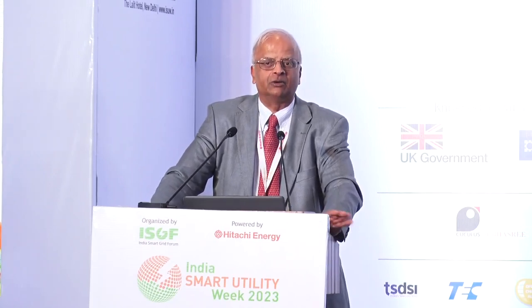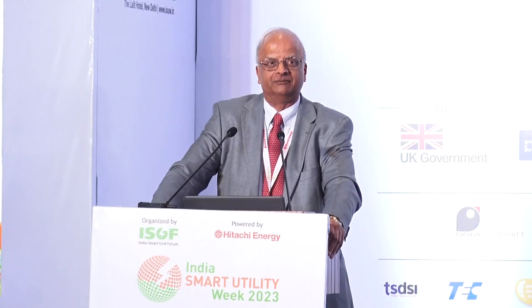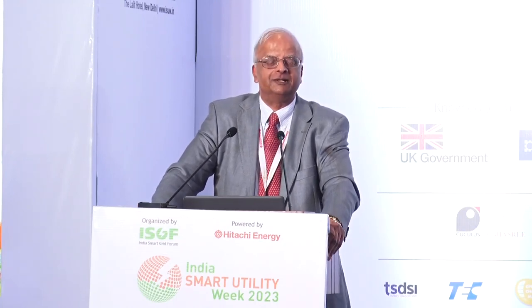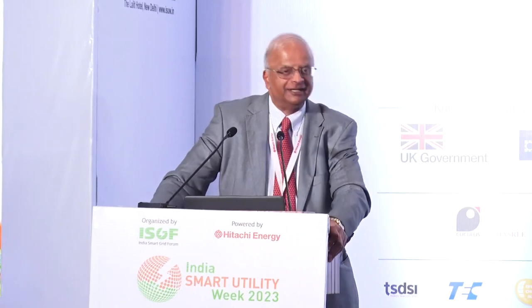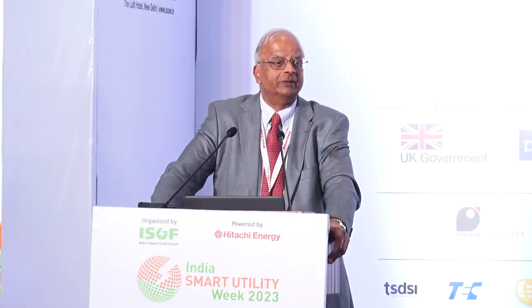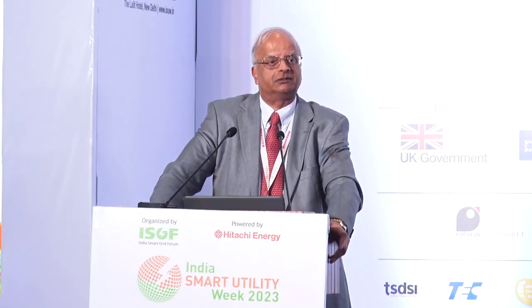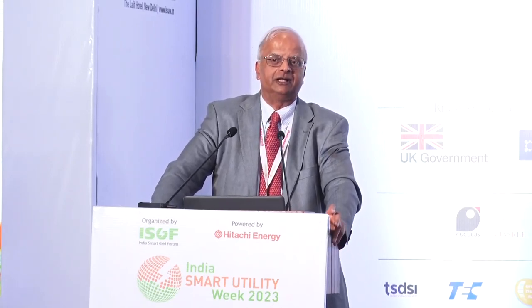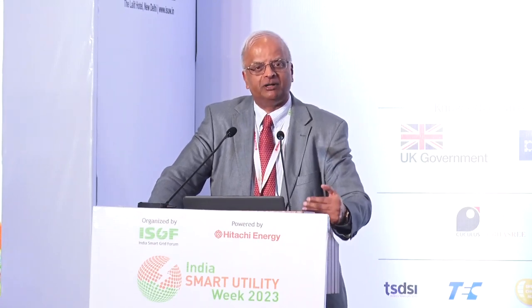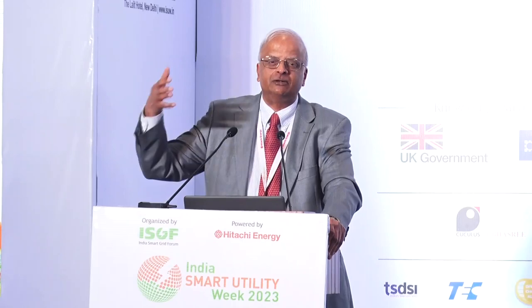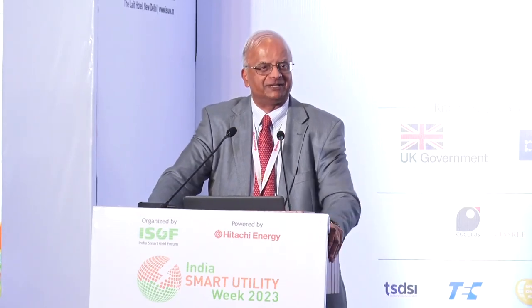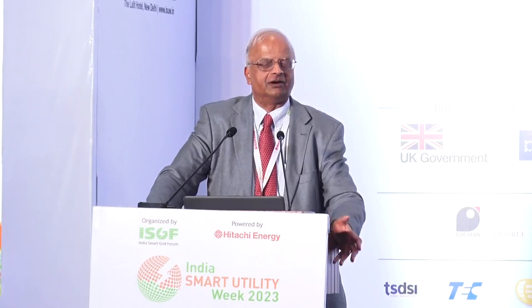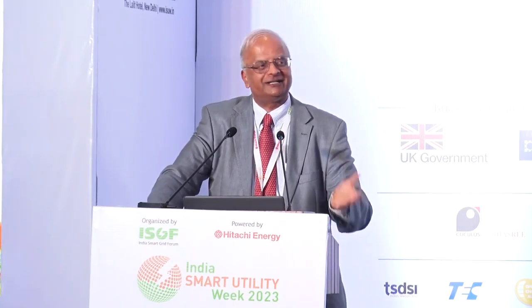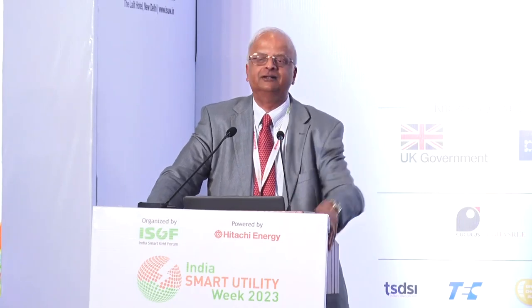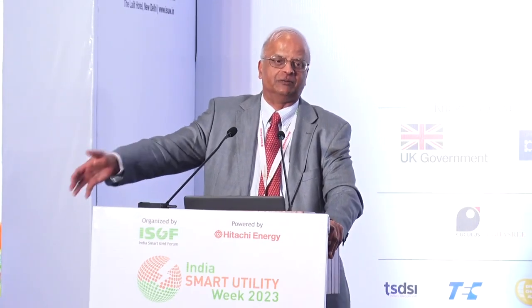The last point is very important. The question, and we in Canada have worked on this for the last four years, is: is the hot oil temperature the real measurement for a transformer? We know the paper insulation is at 90 degrees, the hot oil temperature is 120 degrees. Because it's so difficult to keep measuring with RTDs and others, and it's such an intrusive way of measuring temperature, we basically gave it up and said let's use I-squared-R-T for our hotspot temperature. So today we look at temperatures by computation from the electrical side rather than physically measuring it, because it's so complex to measure.